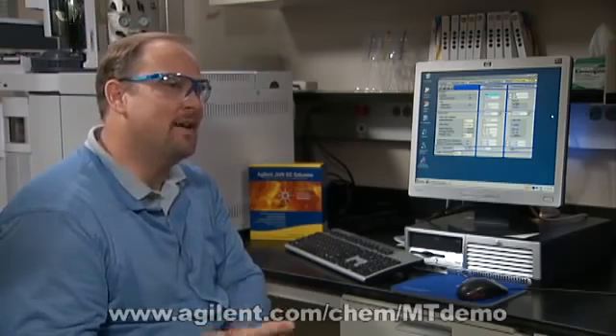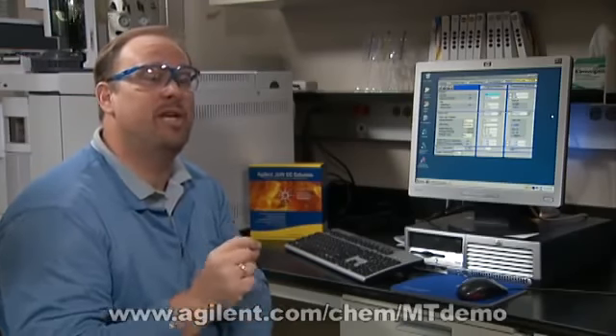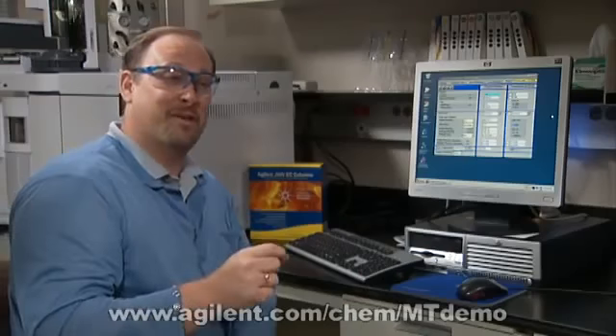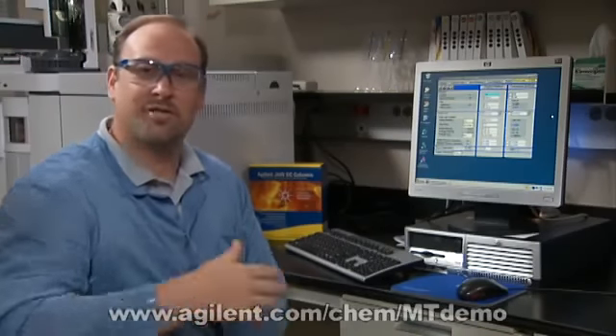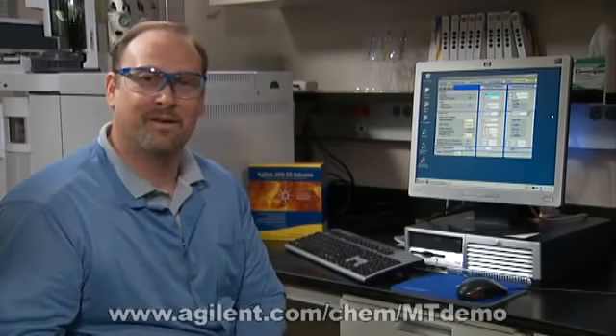At a certain amount of length, it's time to let the instrument know so it won't keep putting the same pressure on the column. If you have the same pressure and you have a shorter length column, you're going through the column faster, but you're still using the same temperature program. You're going to be running through the column faster, and the column temperature won't be as hot as it used to be, and the temperature that all the peaks see will be slightly different. That can move things around.